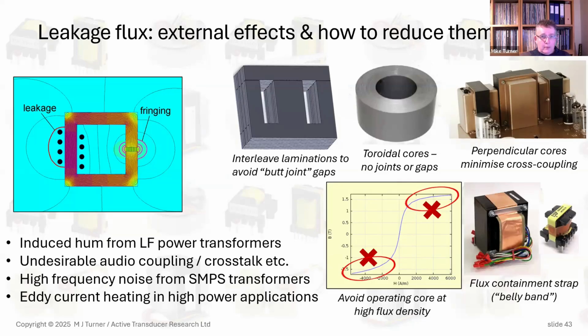And it's good practice in transformers generally to interleave the laminations, like I hope you can just see in that figure there, to avoid gaps in the joints. And the ultimate expression of that, I guess, is the toroid, where you just wind the thing from a continuous strip so there's no gaps at all. Also, if you operate at high flux density, the permeability, remember, of the core drops, and so there's more incentive for the field to spill out because the iron isn't conducting the field as well, if you like.